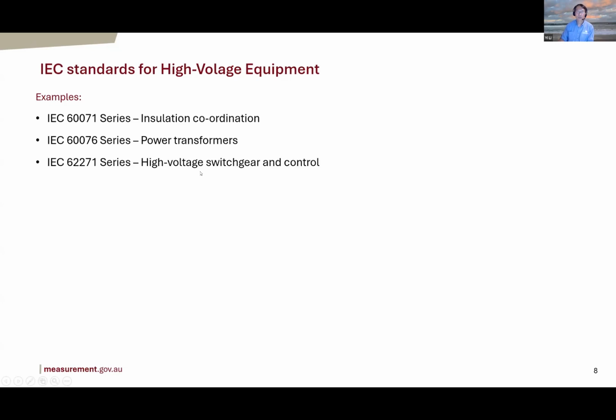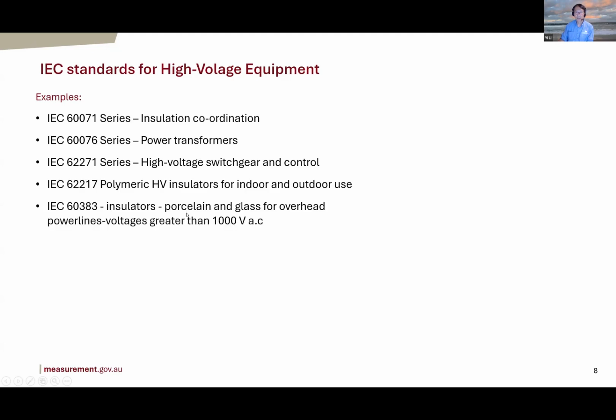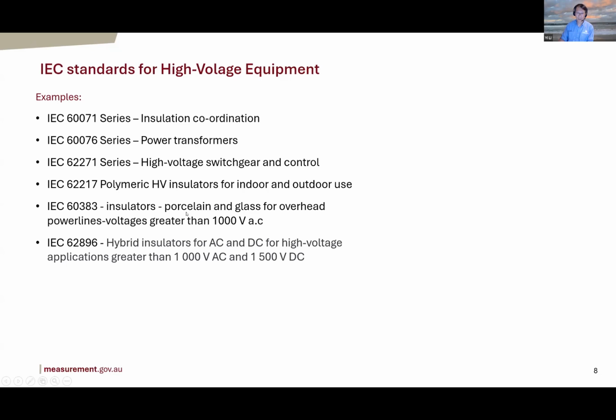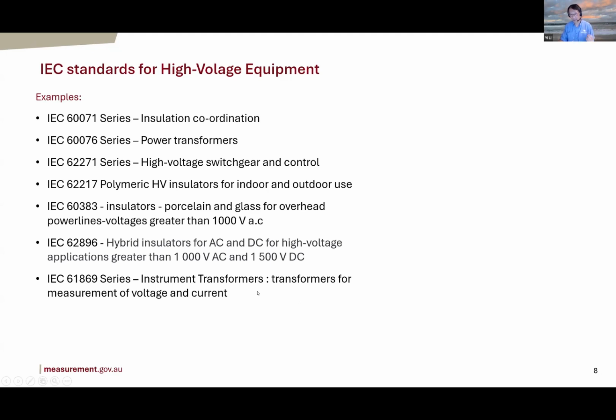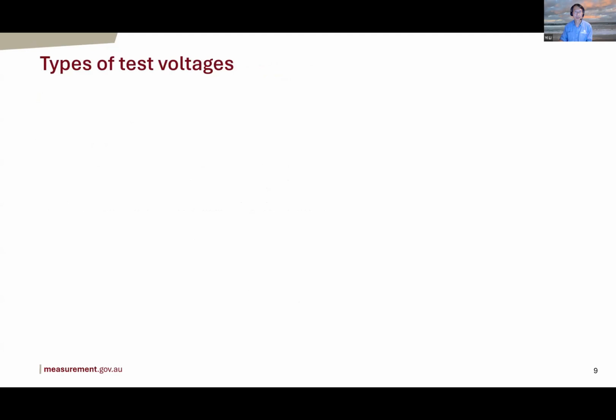You have another important standard for power transformers and switchgear, insulators, the many standards for insulators. They all specify specific tests. And another big series, many, I think now probably more than 10 or close to 20, about the instrument transformers, which are for measuring the current and the voltage. They're not for transport delivery of power. This is for measurement purposes. And nowadays you have digital ones as well. Okay.